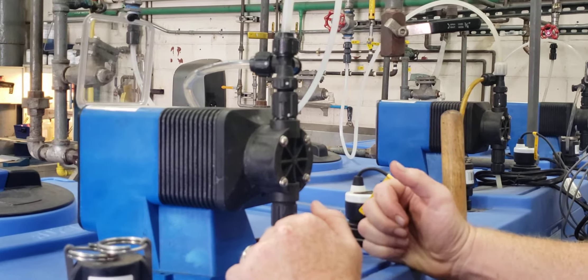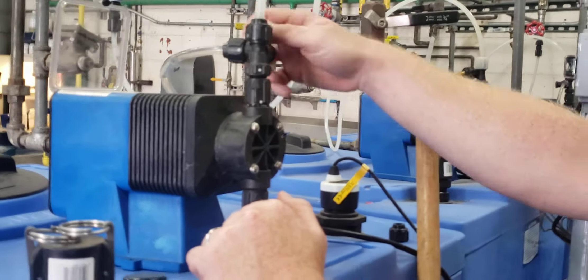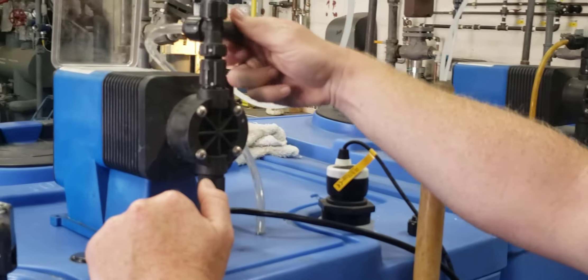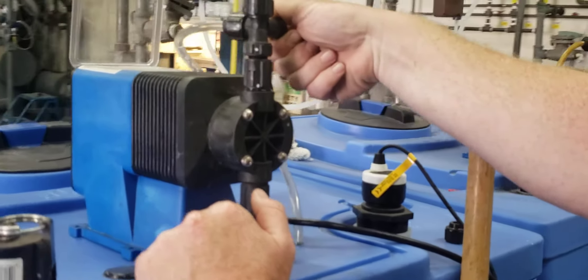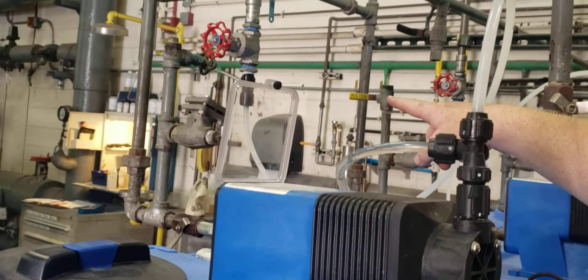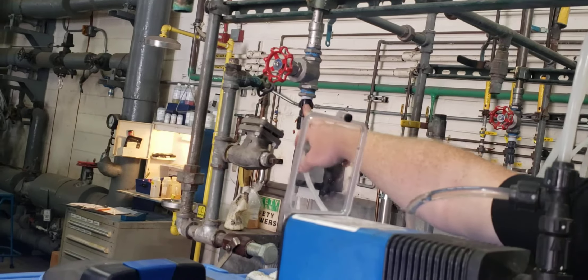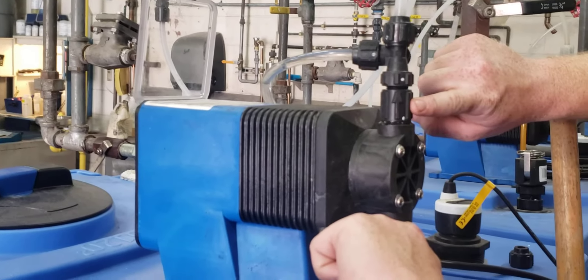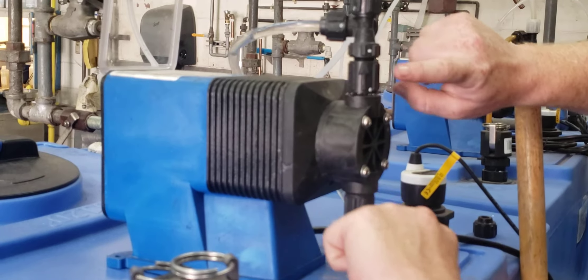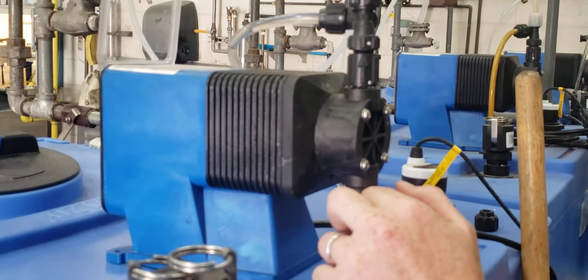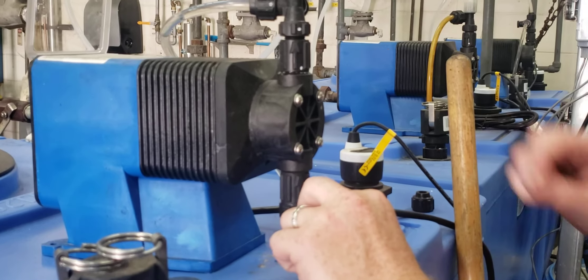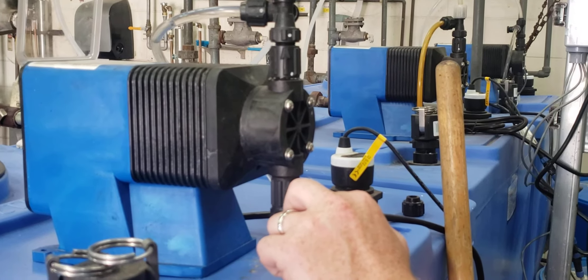Other than that, this is your discharge for if you're going to bleed off. Other things to look for is make sure people don't close the valves on you. There's also a check valve in here, and then there's two little check valves in here. Sometimes those get clogged up or fail with the spring inside as well.